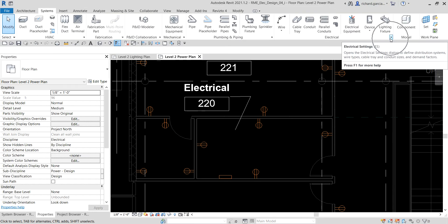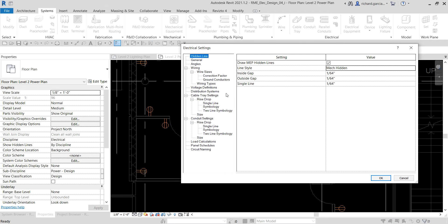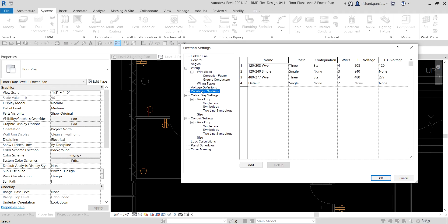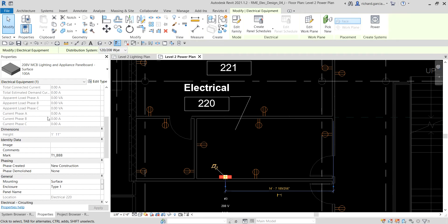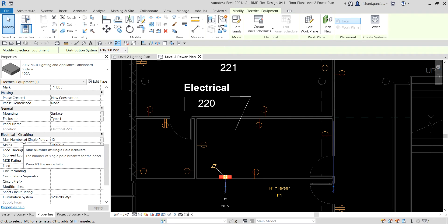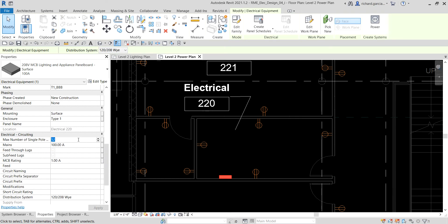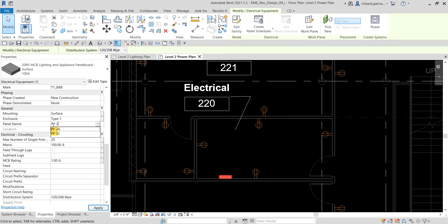If you remember, your distribution system can be set in Electrical Settings — you can type ES, then look for Distribution Systems, and from there see all the distribution systems already created. If I select my panel board, I can change the maximum number of single pole breakers — instead of 12, I'll make it 20 and press Enter to apply. As a best practice, add a panel name. I'll type 'Power Panel-2B' and select Apply.